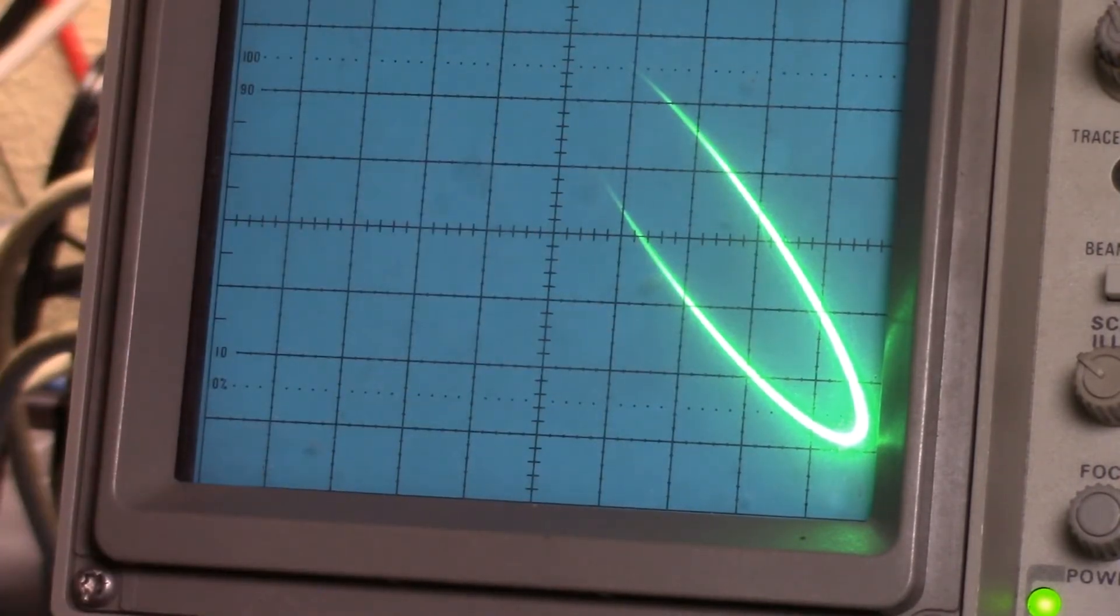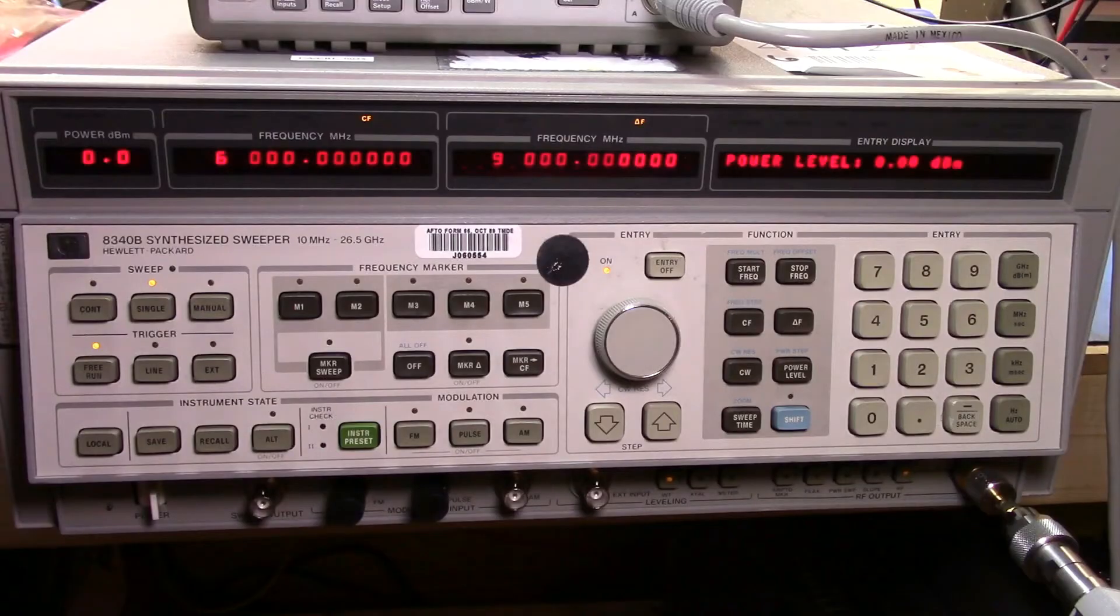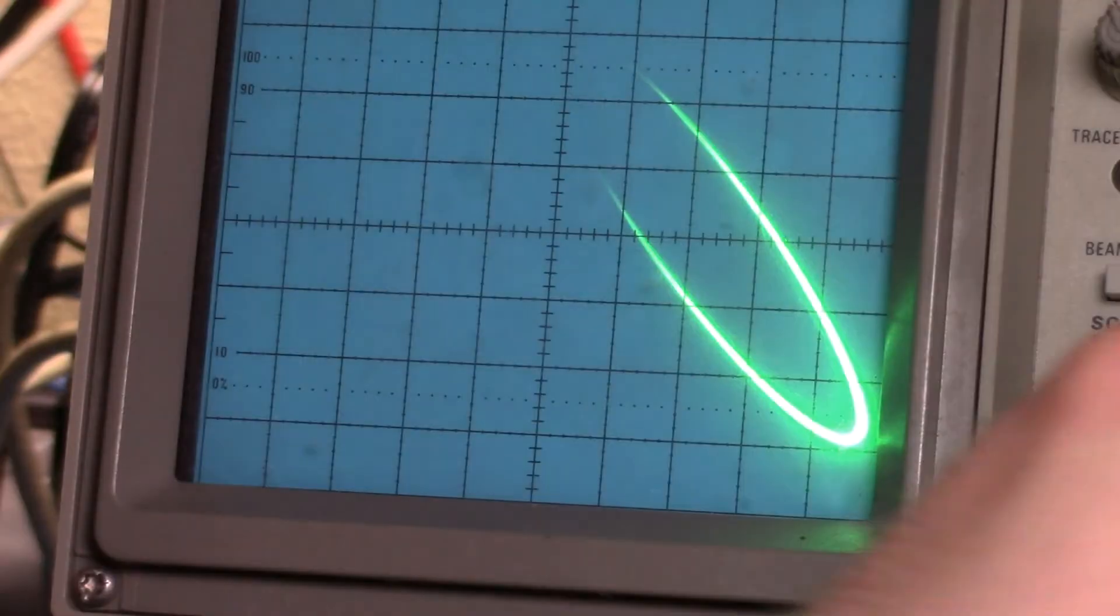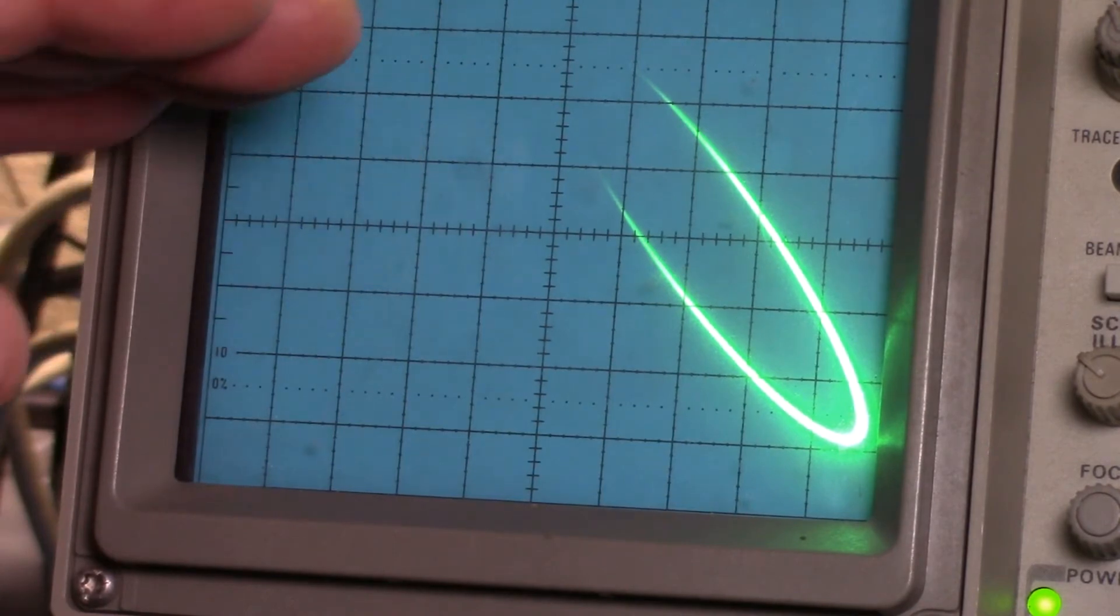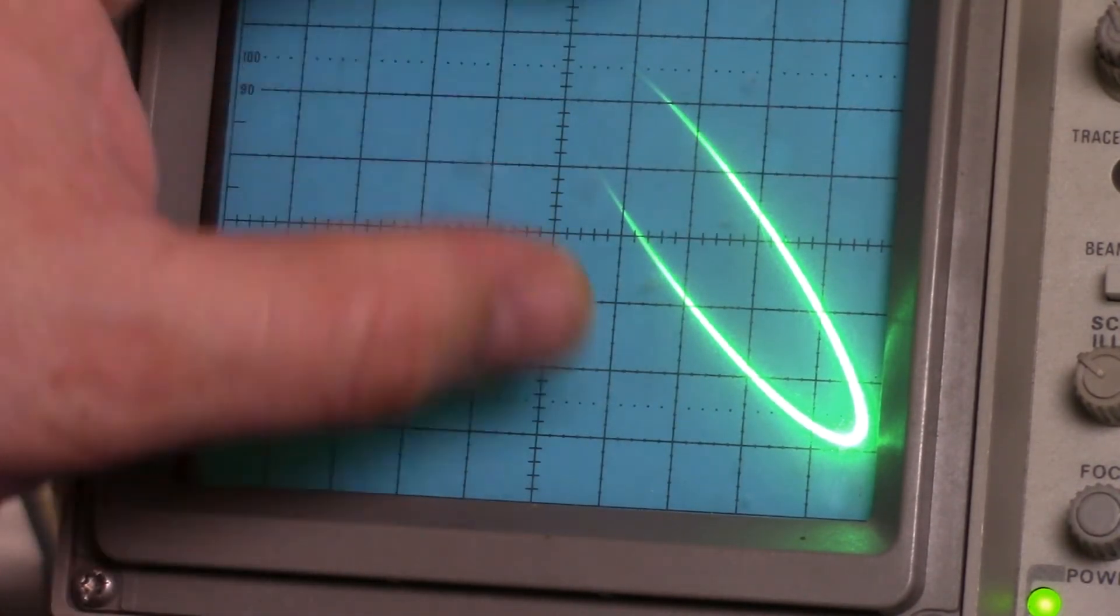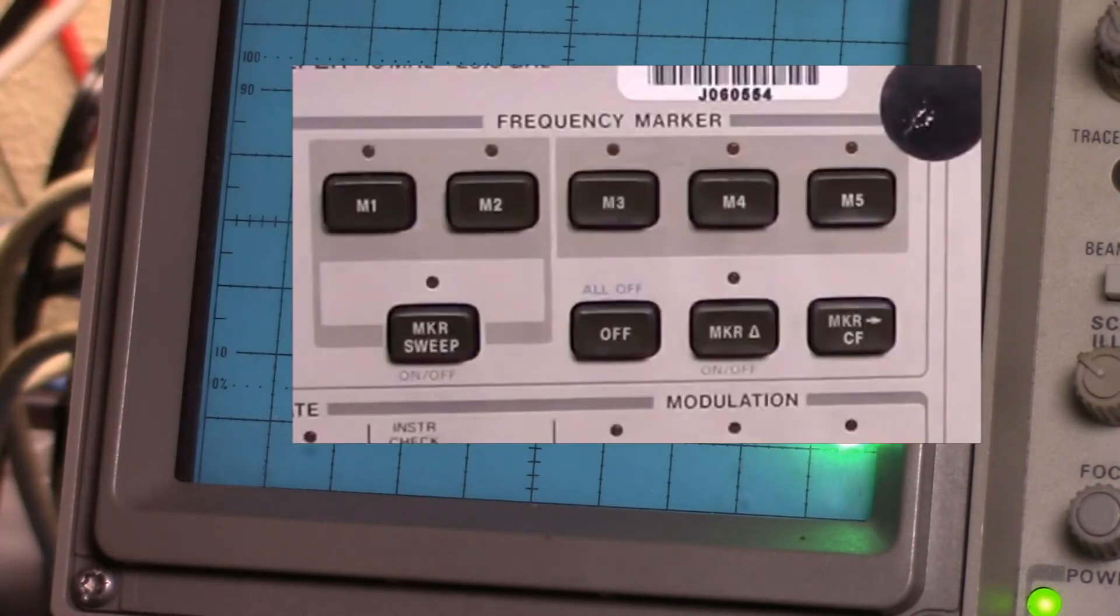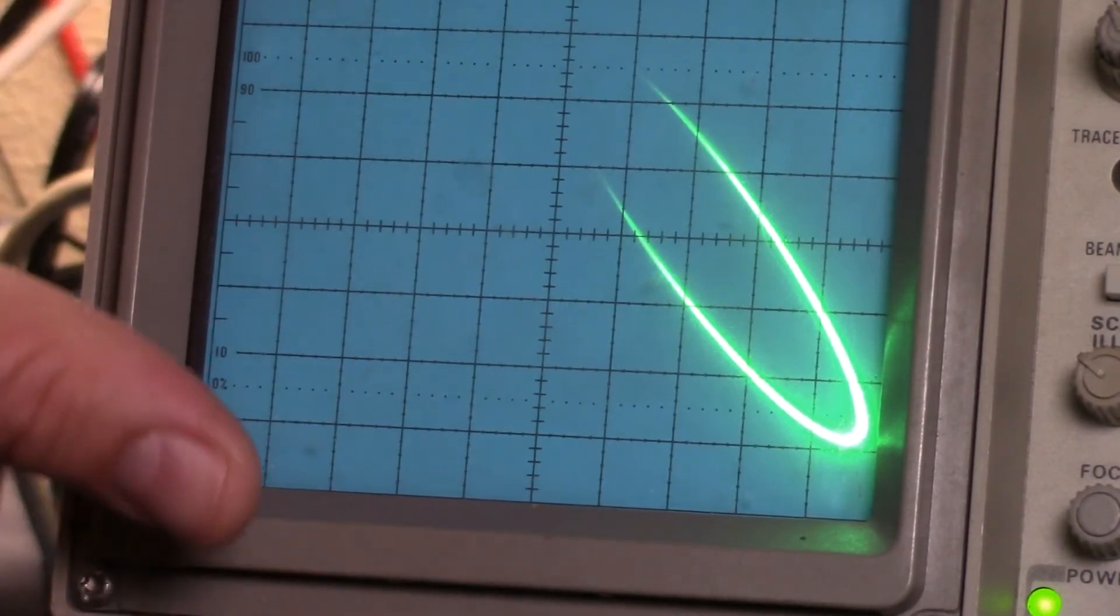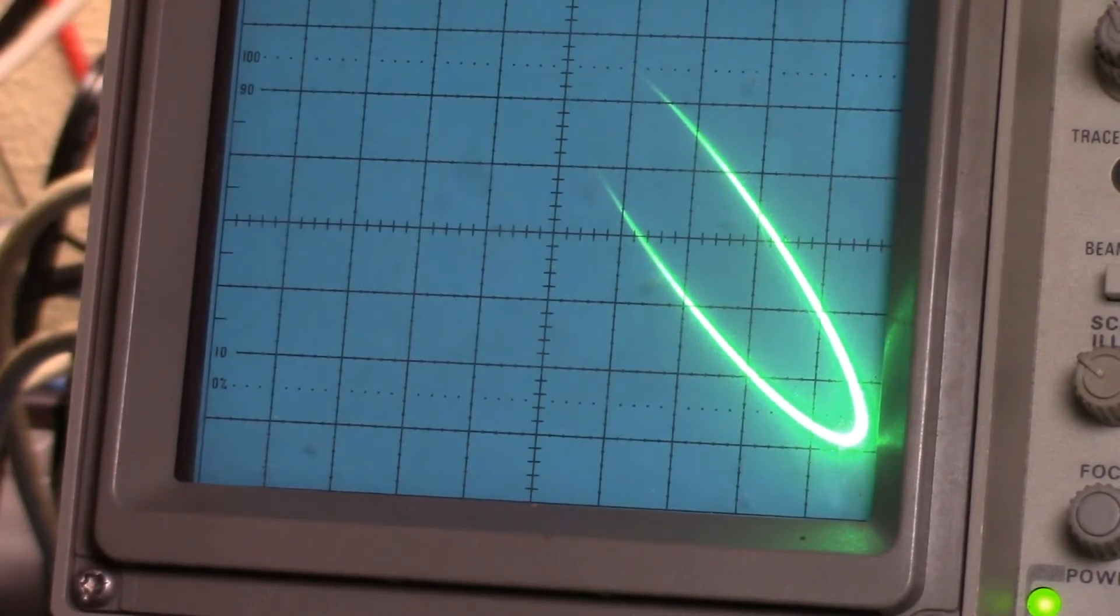And now on the 8340B, that's what I was looking for. I have a crystal detector and on the x-axis, I'll have the sweep time, which is the signal that comes out. It's basically a ramp with a few flat spots as it goes through its sweep from 10 meg to 26. The crystal detector will give me the output level that's coming out of the device. And then I can use its Z-axis output to put a marker on here. And so as I see the signal and I adjust the output of the oscillator, I can get high points on that signal. And then use the marker functions inside the sweeper to come back and find that peak and get the actual signal, the frequency value on that.